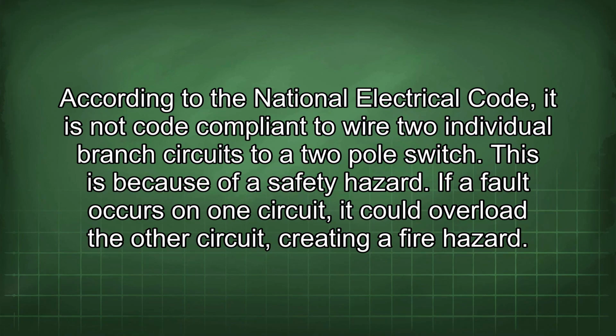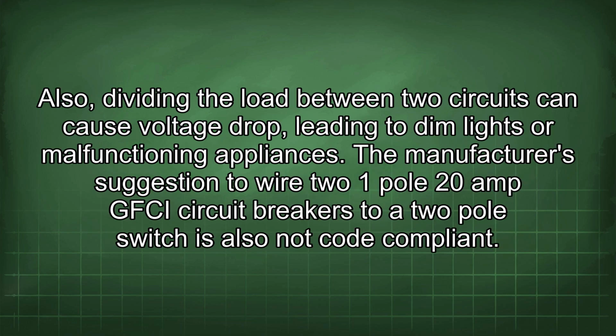According to the National Electrical Code, it is not code compliant to wire two individual branch circuits to a two-pole switch. This is because of a safety hazard. If a fault occurs on one circuit, it could overload the other circuit, creating a fire hazard. Also, dividing the load between two circuits can cause voltage drop, leading to dim lights or malfunctioning appliances.